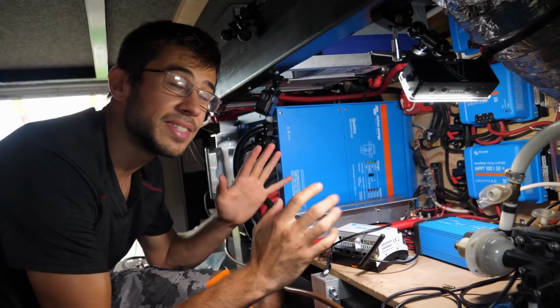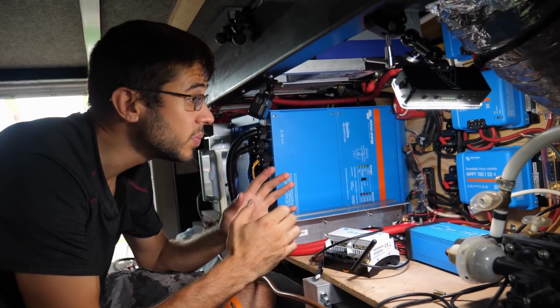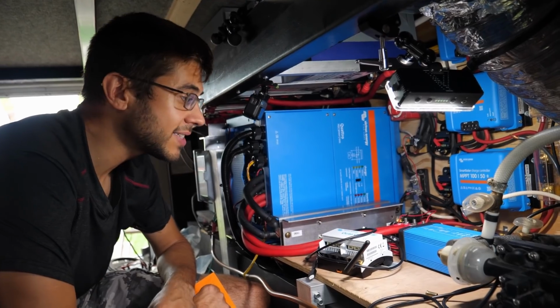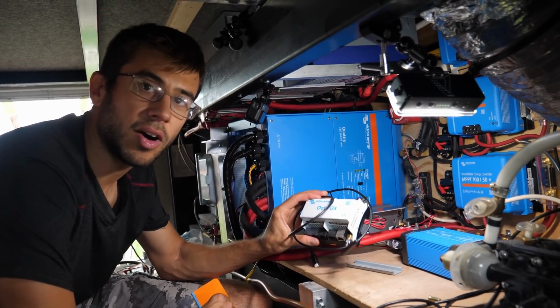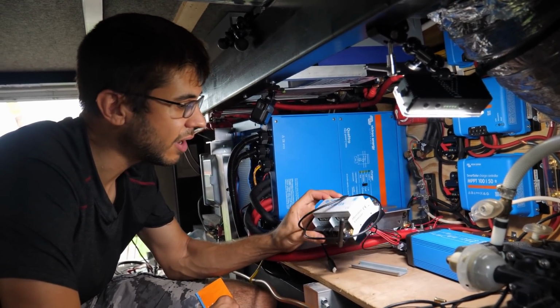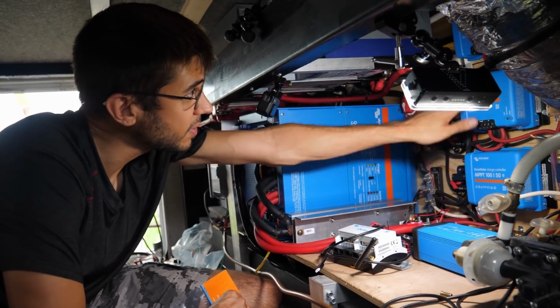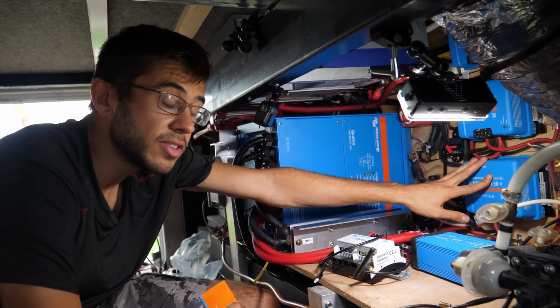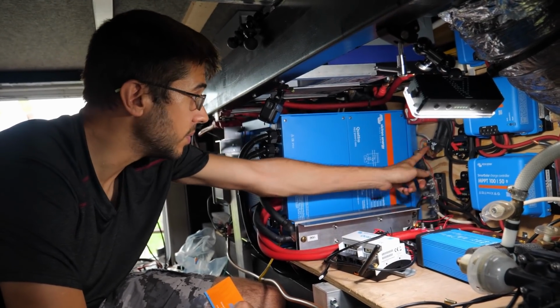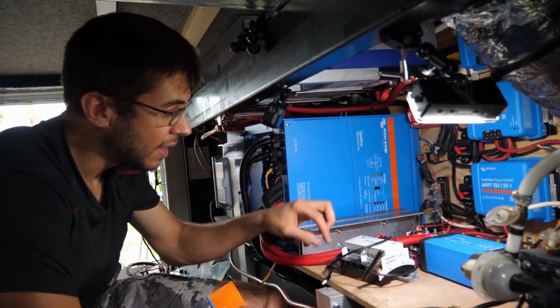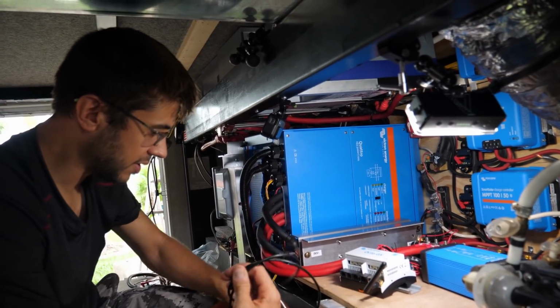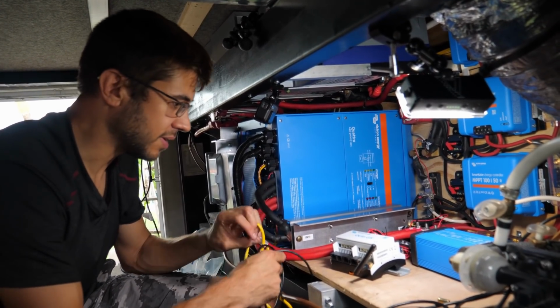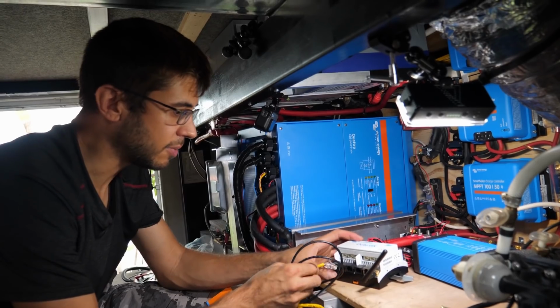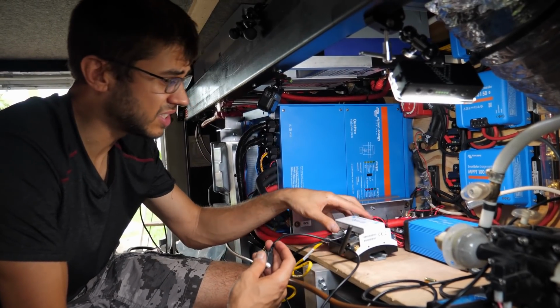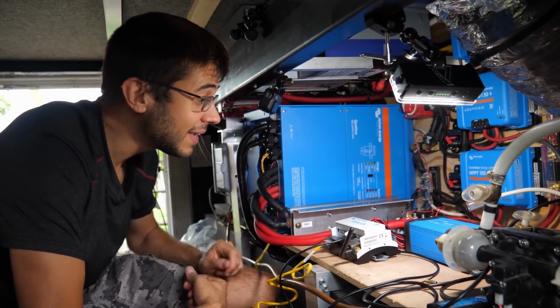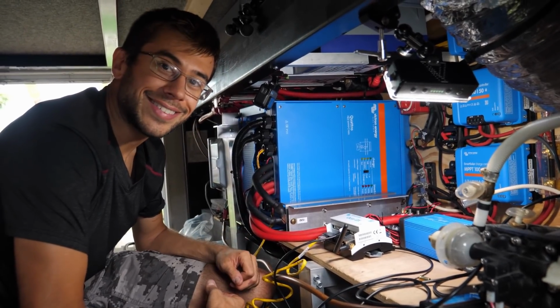So the system is almost done, and I'm super pleased with how it's coming out. The last piece to install is the comms, the brains of the operation. The Octo GX is going to connect to all 3 charge controllers. It's going to talk to the battery meter we installed inside, which talks to this shunt right here, and it's also going to plug into the inverter via this Ethernet type cable. So we're just going to install the Octo GX right here, plug everything in, and now we're going to check it out.